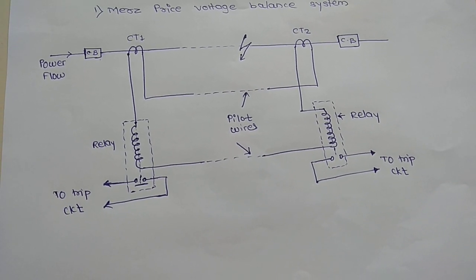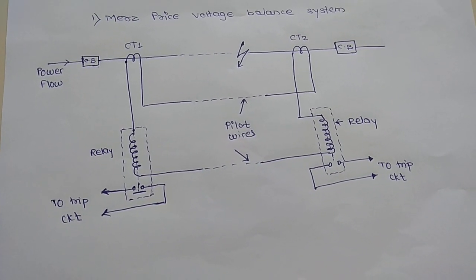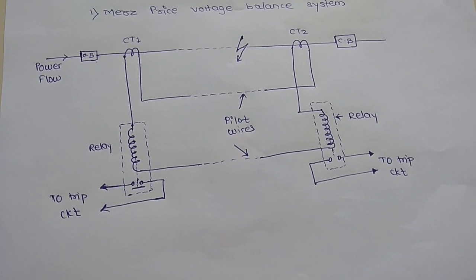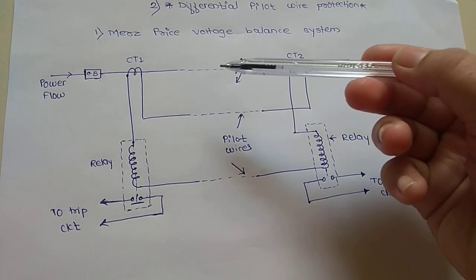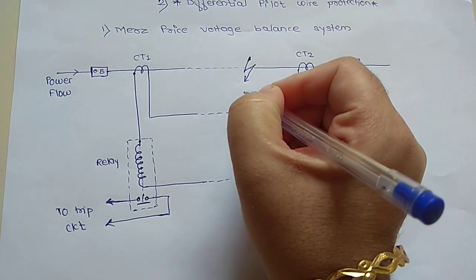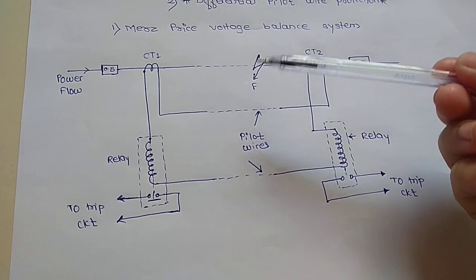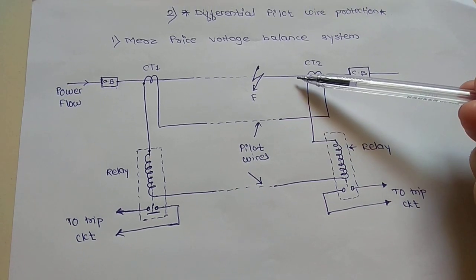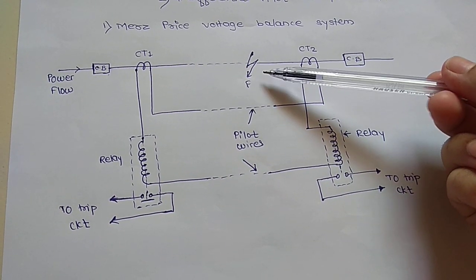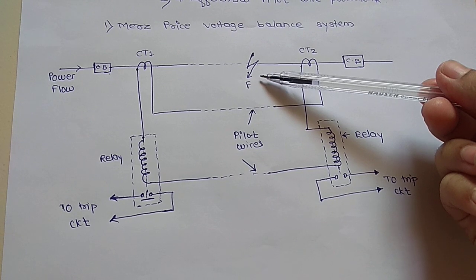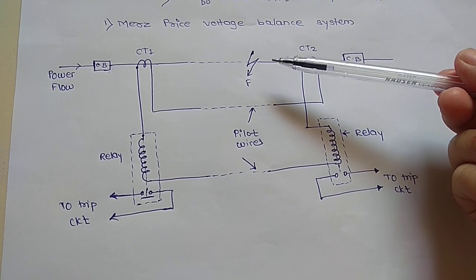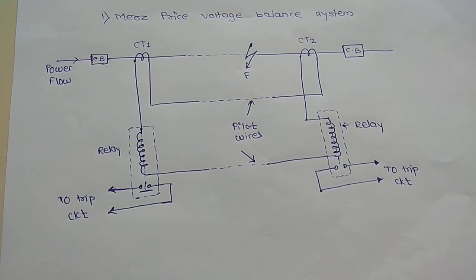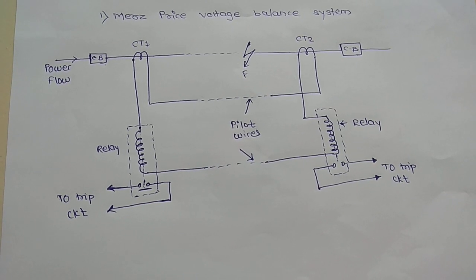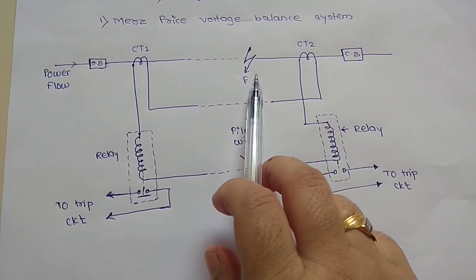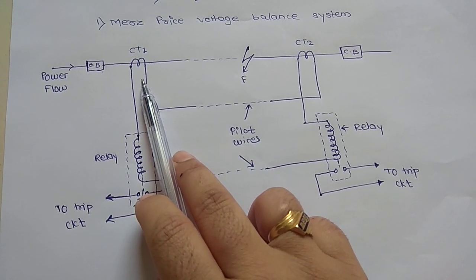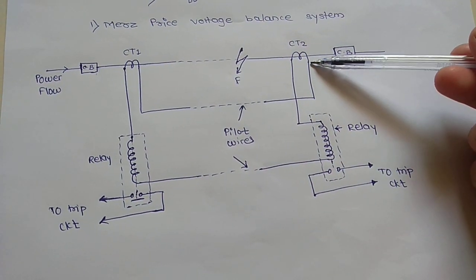Now let's see the faulty condition, when a fault occurs. Consider this is the location of fault on this long transmission line. Due to this fault, the condition is no longer the same, and this causes a greater current to flow through CT1 than CT2.